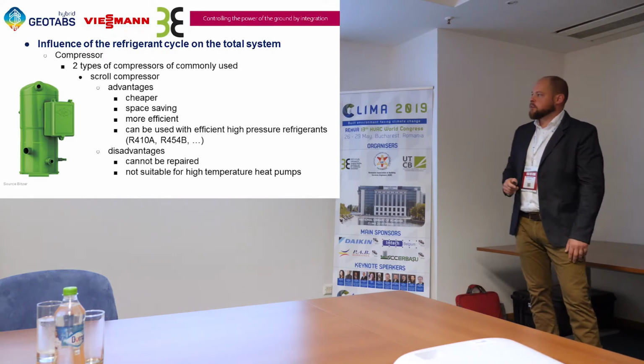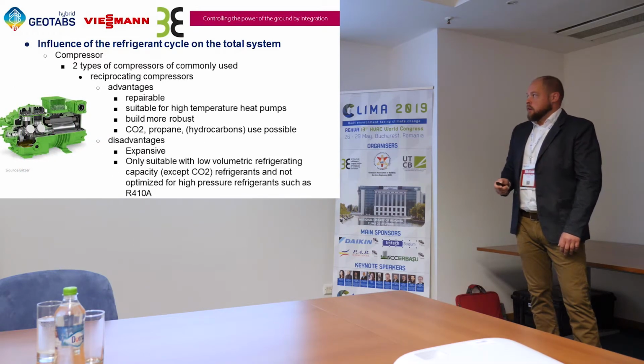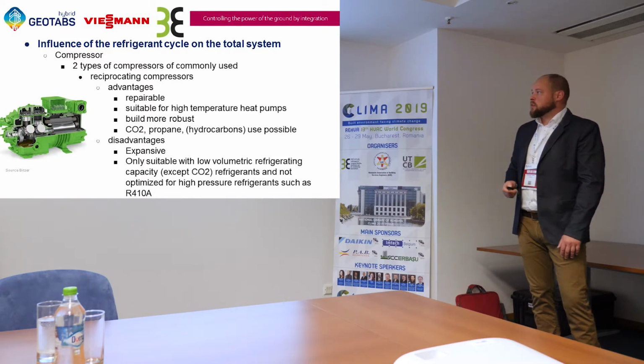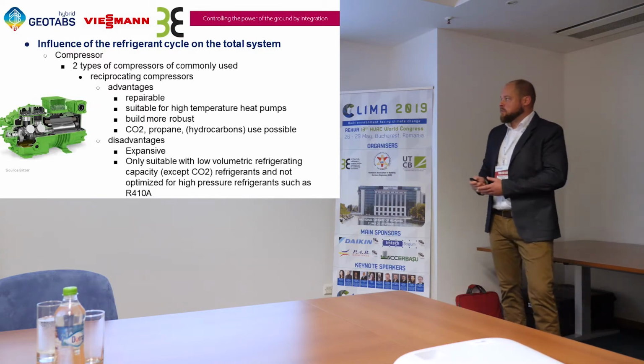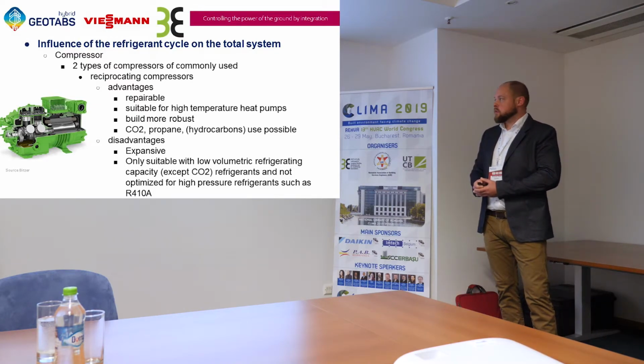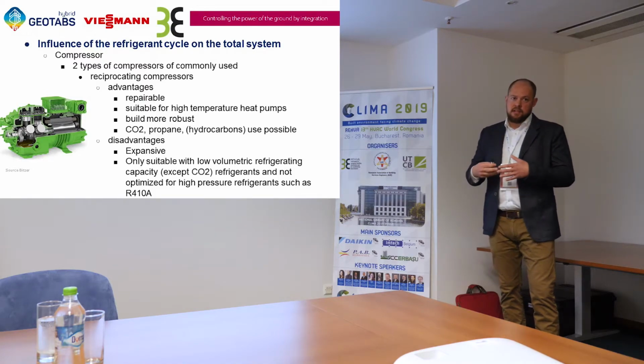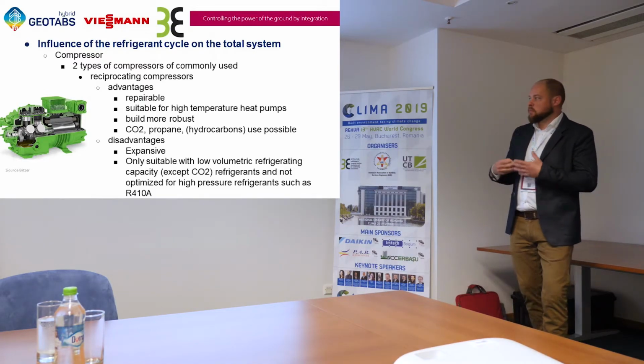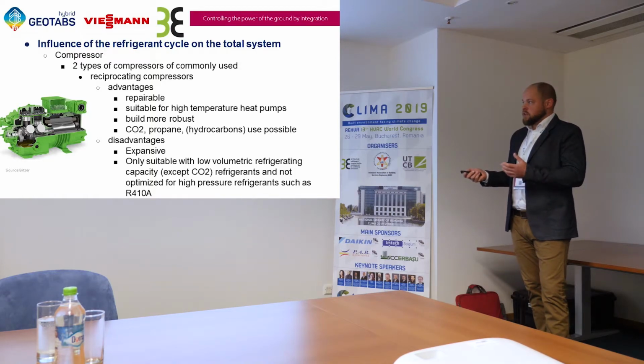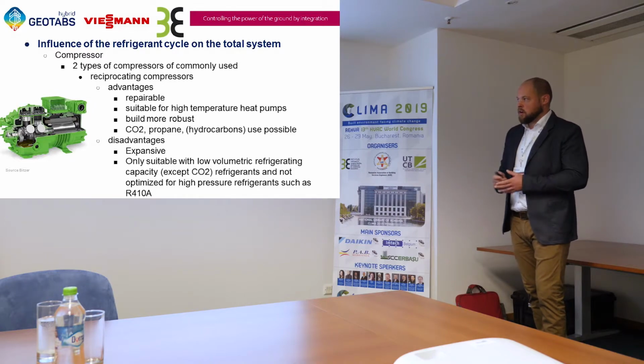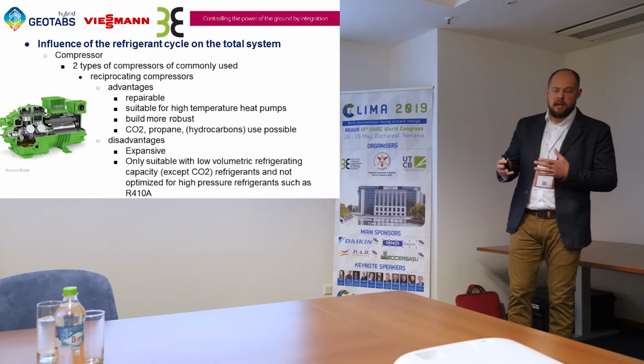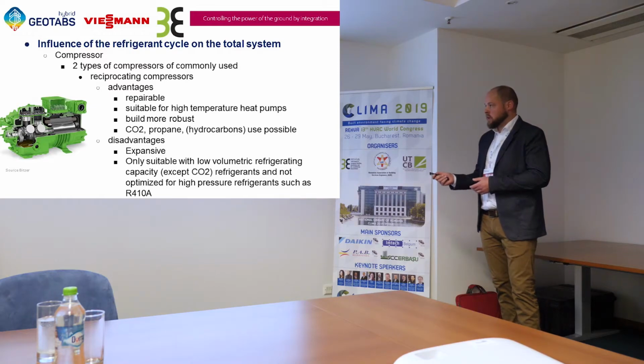Another type is the reciprocating compressor with the pistons, also from Bitzer here in this image. It's a commonly used compressor because it has a lot of advantages. It's repairable, it's suitable for high temperature heat pumps. It's built more robustly, so it can handle more load or more running hours. It's used in CO2 applications, and with propane, R1234ZE or YF, these types of compressors are used.